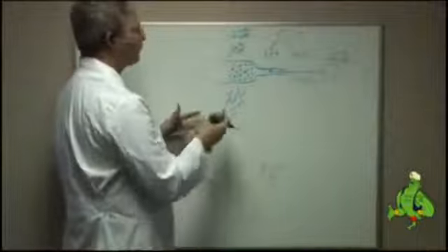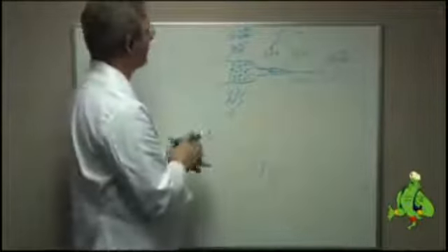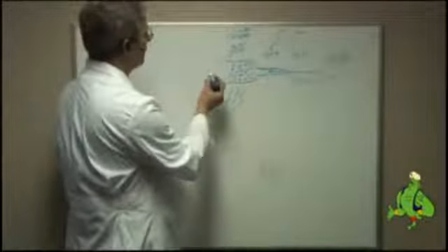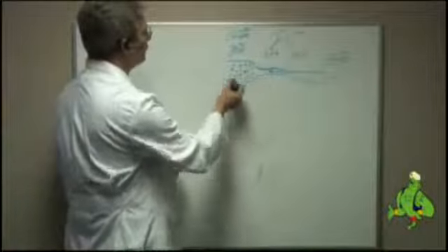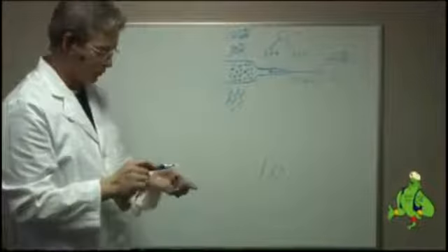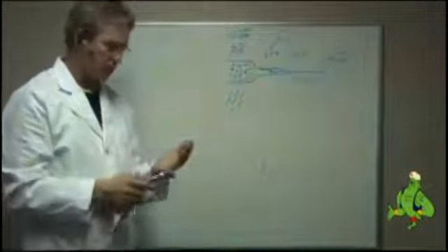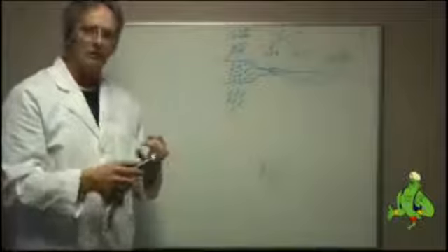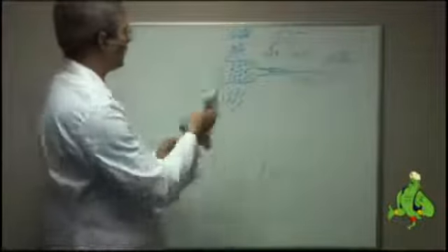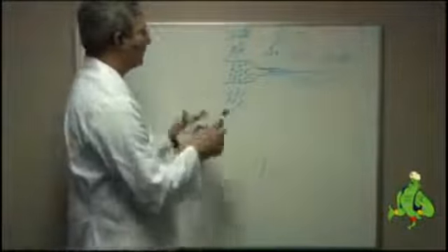So, I know it's all confusing, and I'm trying to do this really, really fast, but our whole goal here is to somehow get rid of this moisture in this entire system, because it is a closed system. All right, the moisture went in when they put in the Freon, the moisture went in when they put in the oil, the moisture went in when they built the system. There's no way to evacuate it all out. You can't boil the whole system out.